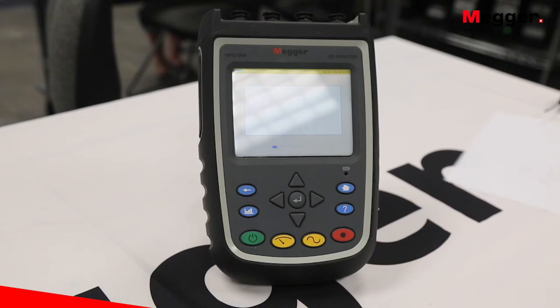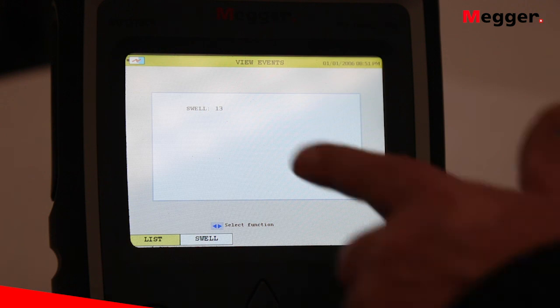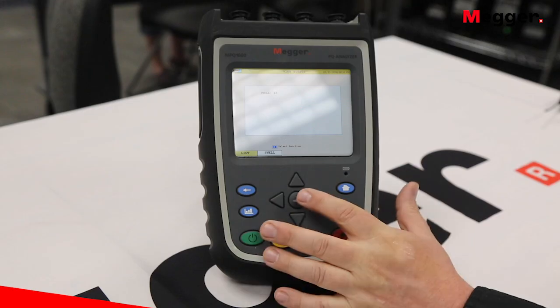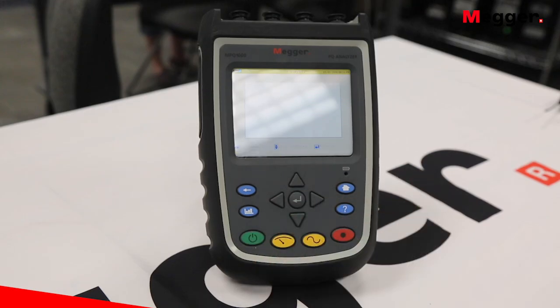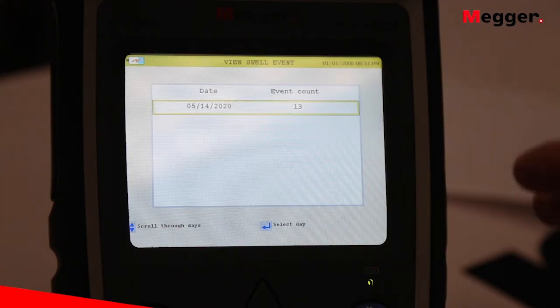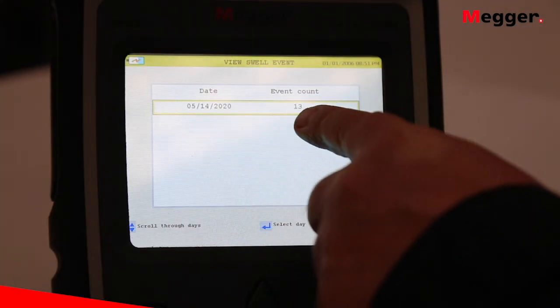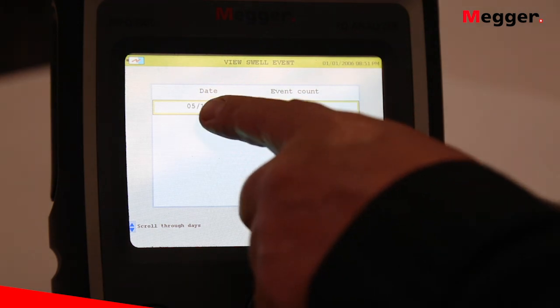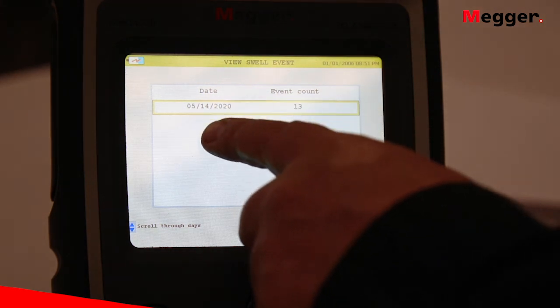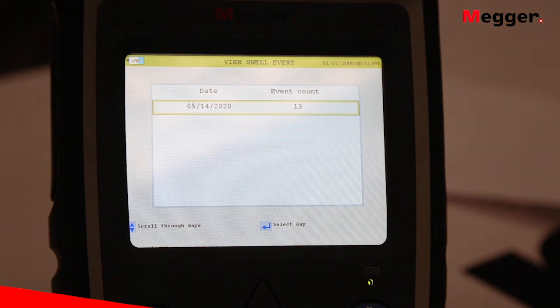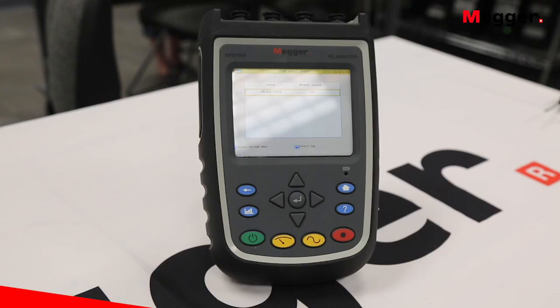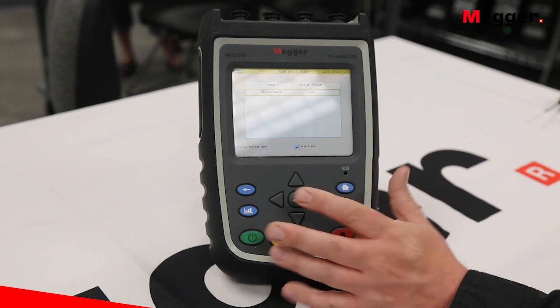The analyzer will first show you how many events were captured, the total number. And we can see that this had 13 events that were captured. So now we're going to select those. And the next thing the analyzer will do is break down the events by the days that they occurred on. So if this recording was multiple days, we would see how many of these events occurred on each of these days, so we could choose the day we want to look at. In this particular recording, it was just one day, so we're just going to choose that day.